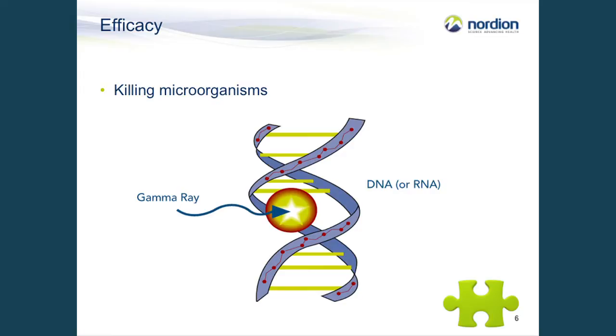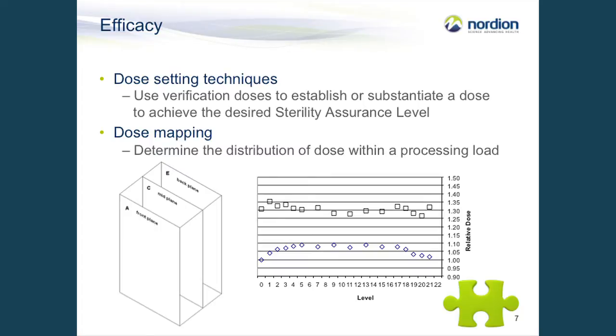Radiation sterilization works by disrupting the DNA of microorganisms present on medical devices. The DNA is damaged, which results in the death of the bug or rendering it non-viable, which means that it can't reproduce anymore. There are various dose setting techniques used to establish the relationship between dose to the given product and the bioburden resistance. This will depend on the number and kinds of microorganisms present, which could be a factor of the manufacturing process and the raw materials used. The sterility assurance level is the probability of a viable microorganism surviving the sterilization process. For most medical devices that come into contact with compromised human tissue, this is one in a million.